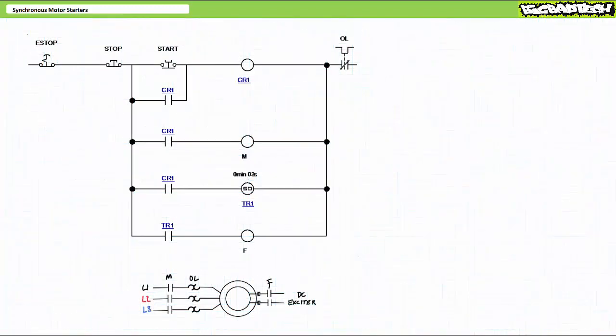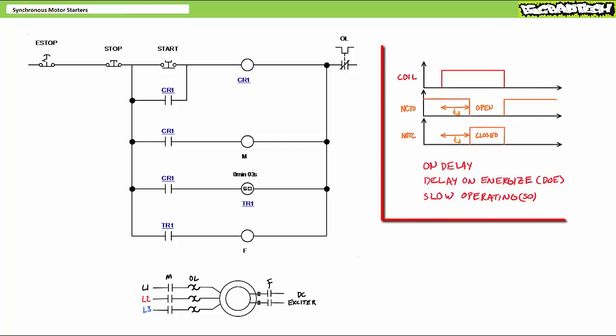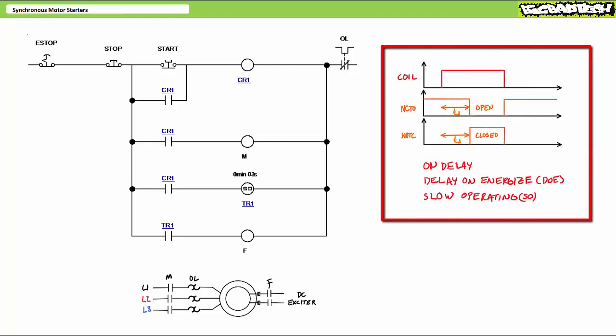Consider a hardwire relay-based ladder logic implementation of a synchronous motor starter with amortisseur windings employing a timer executing the on-delay function. Viewers will recall an on-delay function, sometimes called a delay on energize or DOE or slow operating or SO timer, exhibits a customizable delay between when the timer coil is energized and when the associated contacts change states.